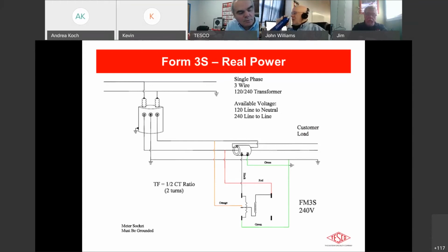John, a very big use for this type of installation would be a farm, where you've got a line coming in and out to the farm and a CT up on the pole, and then it's called a CMS, a central metering system. And then above the metering, you would branch off to your barn and your house and your drive shed and a bunch of other things. So these things are real big out in the rural applications.